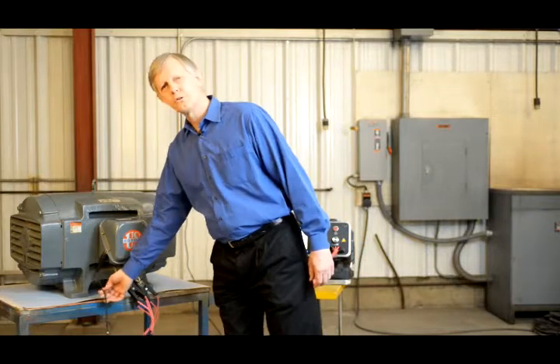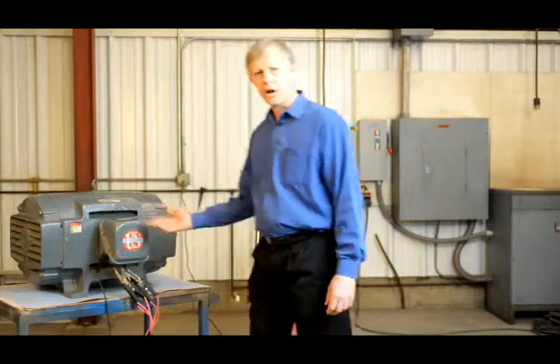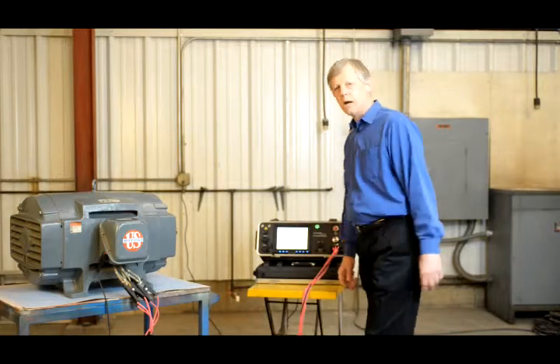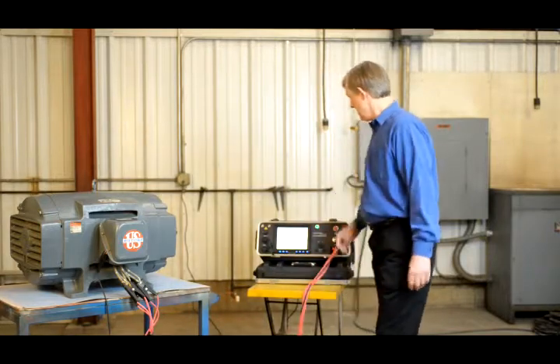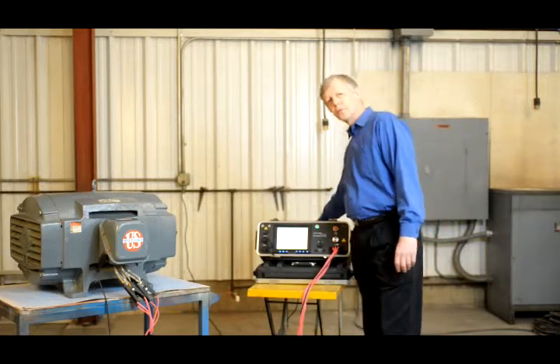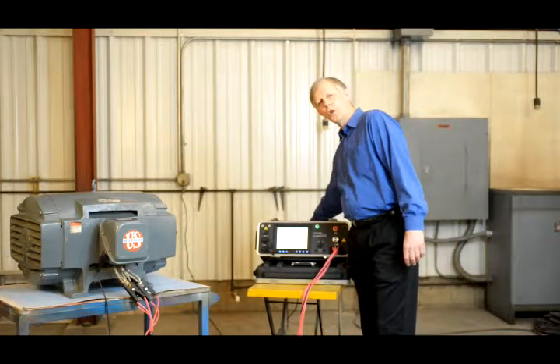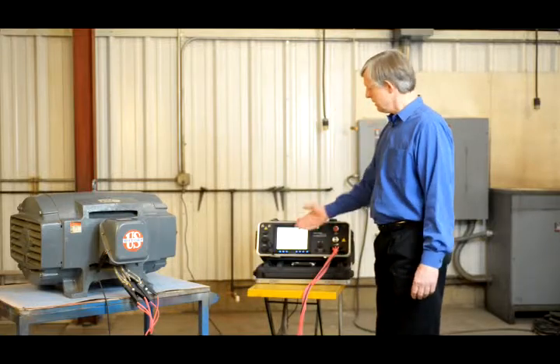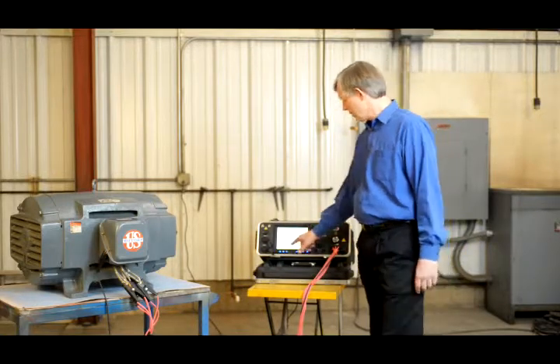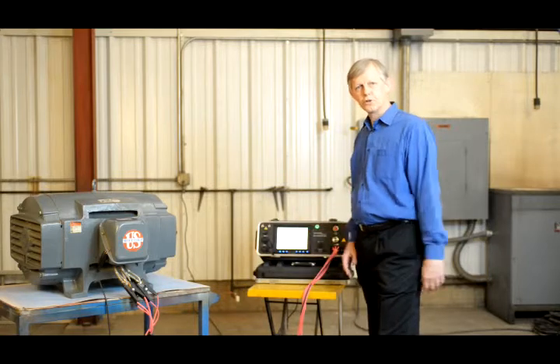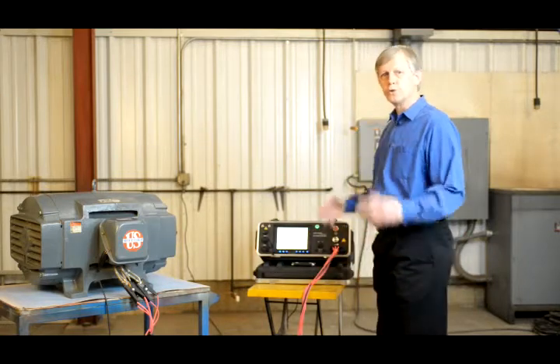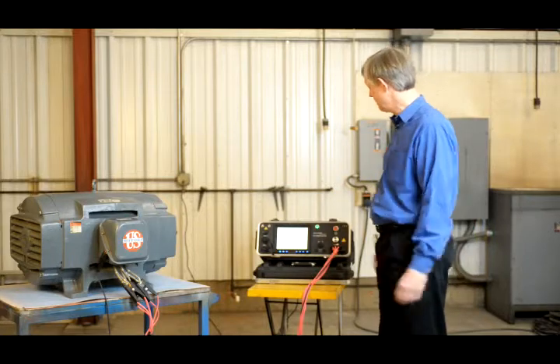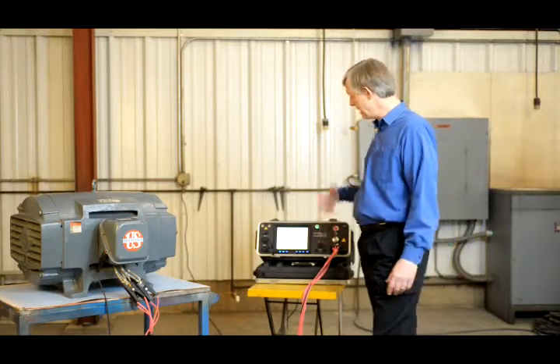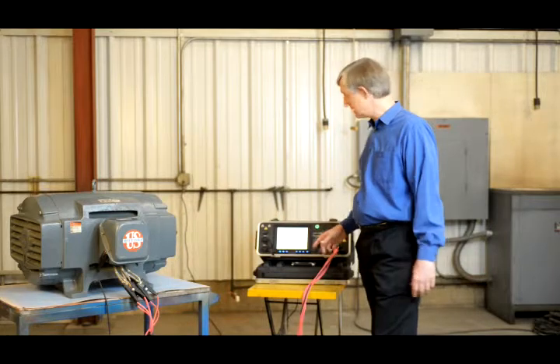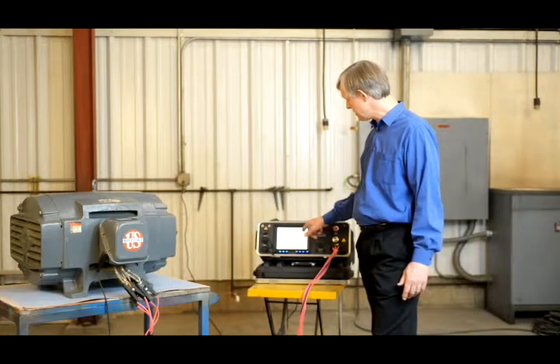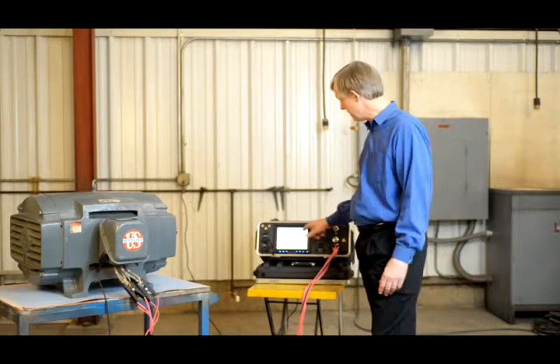We do have a ground lead connected to the frame, which is required in the high voltage tests. When you turn on the ITIG 2 with the main power on-off button in the back of the case, this screen comes up. You click the start button and we are now on the first screen of the ITIG 2, used both in automatic mode and manual mode. Since we're in manual mode and we are going to do tests without saving the data, we click this button up here that says test without data save.